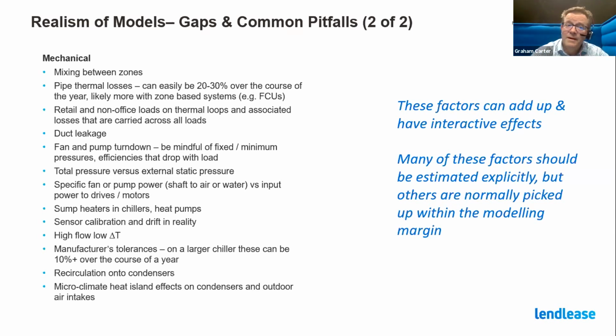We don't think about reticulation losses that much. A mechanical engineer might think they're 1 to 2% at design point, but if you put that across the year, allow for the warm-up loads and pull-down loads, part load operation, you're going to find it's at least 20–30%, if not more, when you've got zone-based systems like fan coil units.